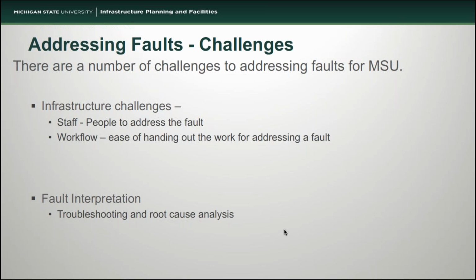We also have not established a good workflow for how to handle faults. In an ideal world, a fault would trigger and it would get directed to the appropriate entity's workbench. They would automatically pick up that work order, run out into the building, and address the fault. They would record what the problem was and then come back and tell us, closing a loop that gives us root cause analysis. It's not something that has been well established yet. We're still working our way through what that should look like. The other challenge in addressing faults is interpreting them. We can have a rule that detects a particular thing, and we can assume that it is a particular problem, but that's just not always true.